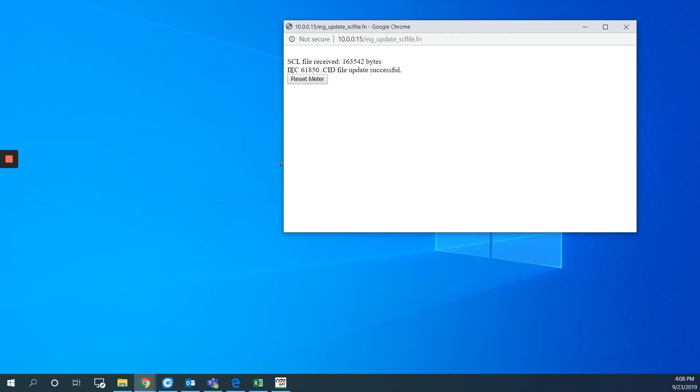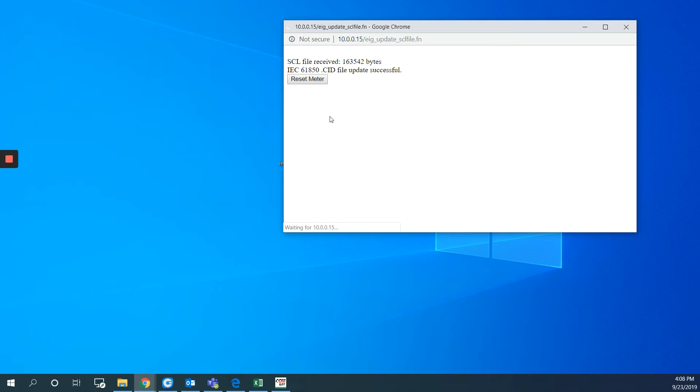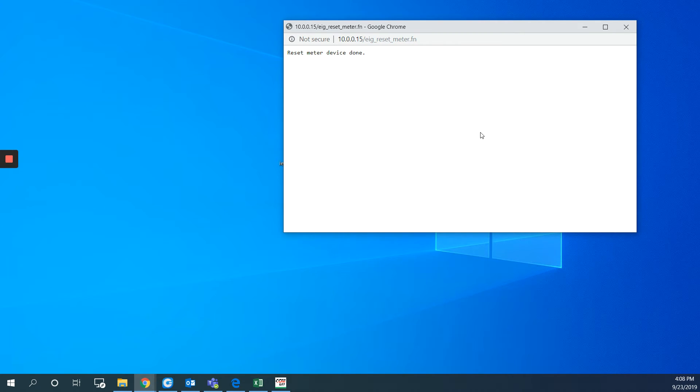So I will get this message saying the IEC 61850.CID file update successful. And now I will hit reset meter. Which is basically a software rebooting. So the meter would take just a minute or less for rebooting.